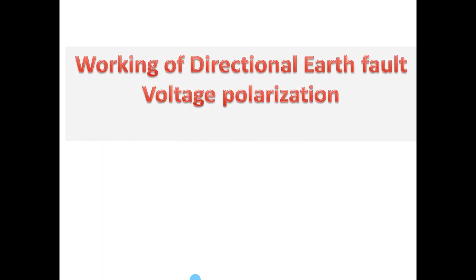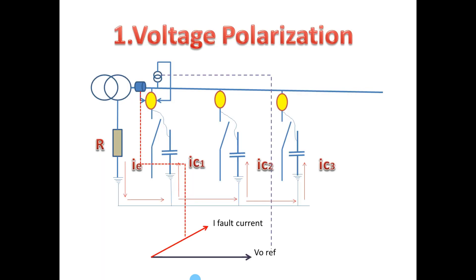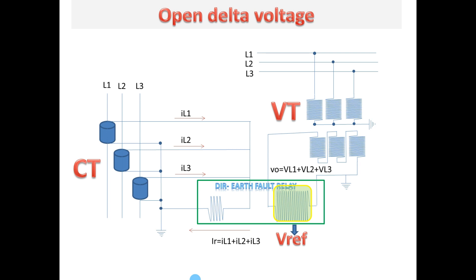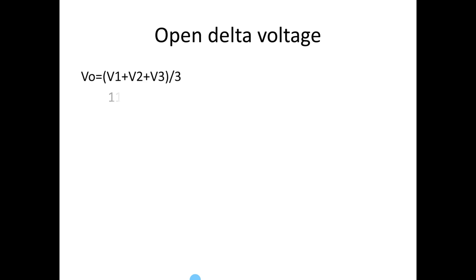This is the diagram for the voltage polarization method. The CT may be a phase CT or neutral CT. For this connection, first we are going to see an open delta voltage. Normally, if all three phase voltages are balanced, this open delta will be zero.